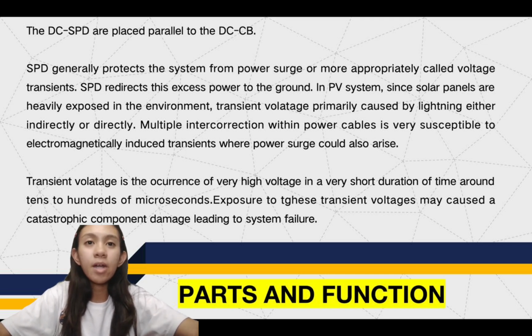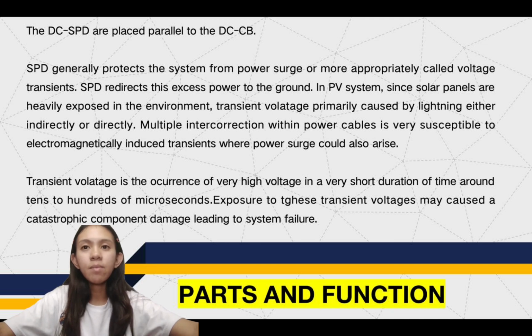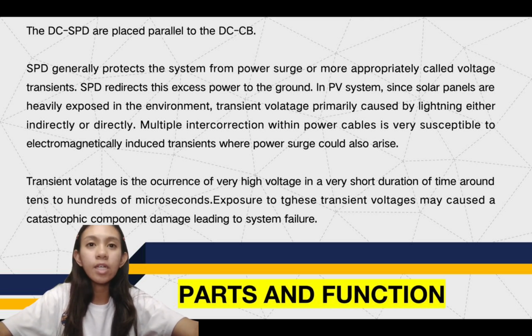Transient voltage primarily caused by lightning, either indirectly or directly. Multiple interconnection within the power cables is very susceptible to electromagnetically induced transients where power surge could also arise. Transient voltage is the occurrence of very high voltage in a very short duration of time, around tens to hundreds of microseconds. Exposure to these transient voltages may cause a catastrophic component damage leading to system failure.